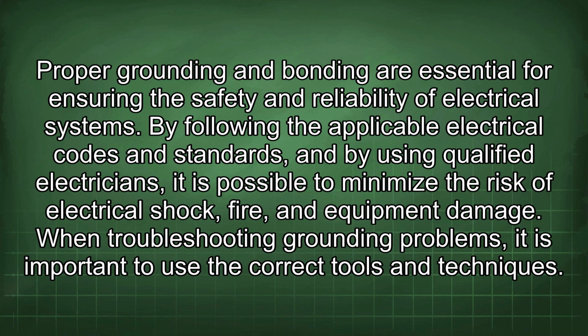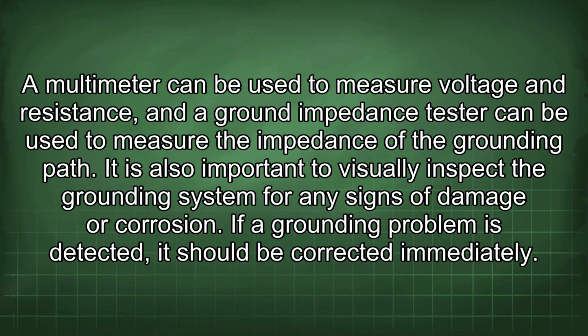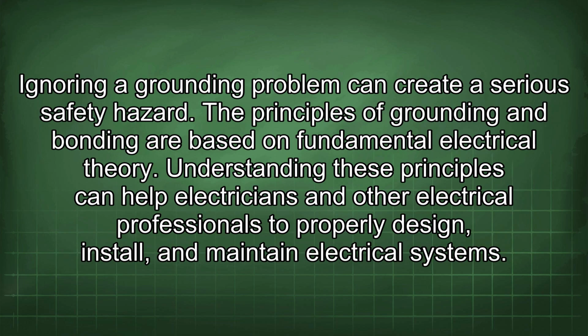When troubleshooting grounding problems, it is important to use the correct tools and techniques. A multimeter can be used to measure voltage and resistance, and a ground impedance tester can be used to measure the impedance of the grounding path. It is also important to visually inspect the grounding system for any signs of damage or corrosion. If a grounding problem is detected, it should be corrected immediately. Ignoring a grounding problem can create a serious safety hazard.